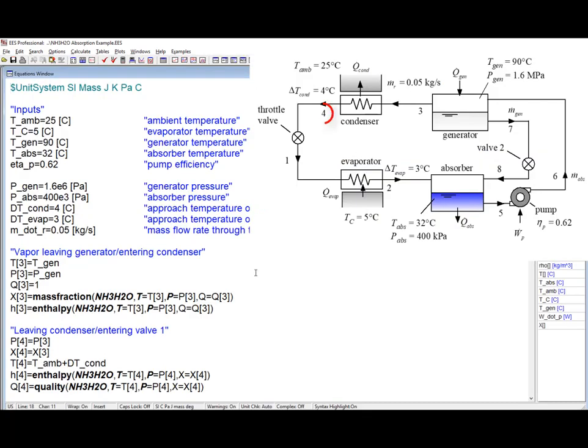The flow passes through the condenser to state 4. We are going to assume that there is no pressure loss in the condenser and the mass balance on ammonia for the condenser requires that the mass fraction of ammonia not change. The temperature leaving the condenser here is fixed by the approach temperature difference of the condenser and therefore state 4 is fixed by P, X for mass fraction and T.